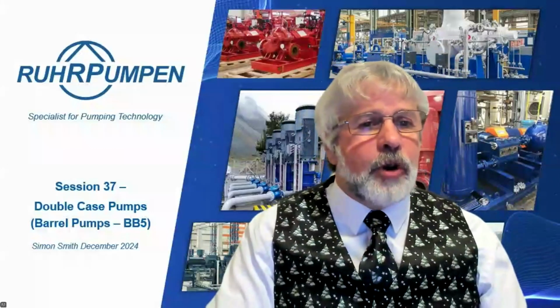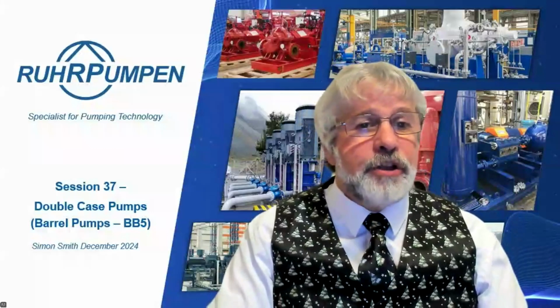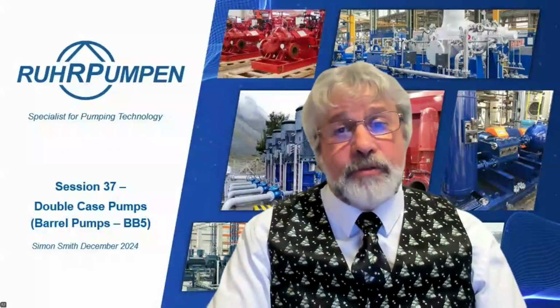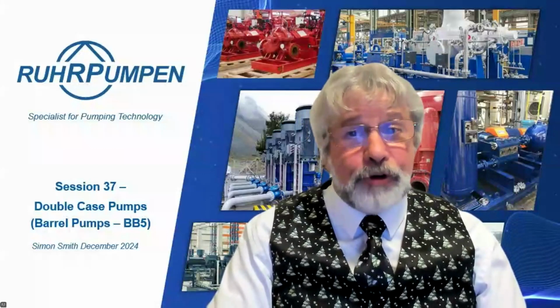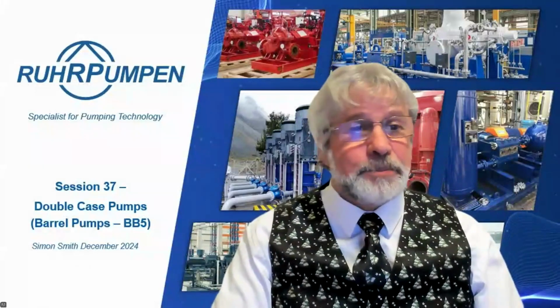Anonymous attendee says, please explain the difference in mechanical seals for clockwise and counterclockwise direction for the 2 sides of the pump. They'll be almost identical. It's just the pumping ring will be designed to operate in the opposite direction.